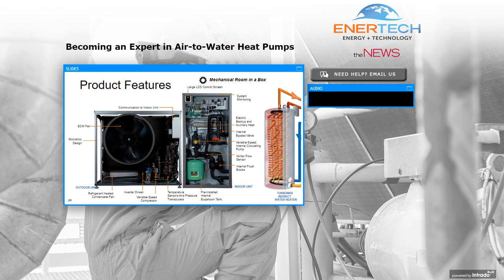On the far right, we show the TurboMax indirect water heater, which is what we're using with this product. It's backwards from most indirect water heaters in that we have the heat pump loop water in the tank, and we have the domestic water circulating through the heat exchanger. So that gives us a lot more mass to work with. And even though we can provide up to 135 degree water leaving this heat pump, we're still not running 160 or 180 degree water like a boiler might. So having this reverse piping gives us a huge advantage and makes heat pump water heating really, really advantageous from a cost standpoint.